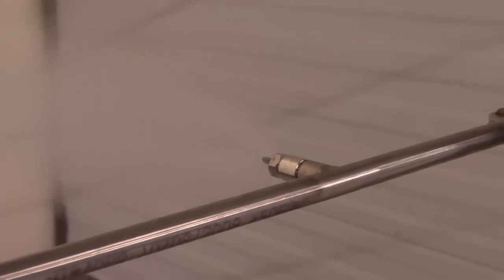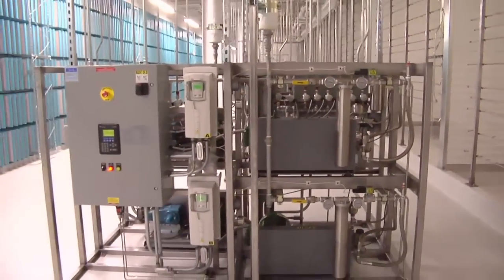This MeeFog system essentially is a high pressure pump. There's a set of nozzles up here. The nozzles come on depending on the amount of moisture you want to put in the air. I chose this section because a few of them are running here. All or some or none will be running depending on whatever the conditions are that warrant it.